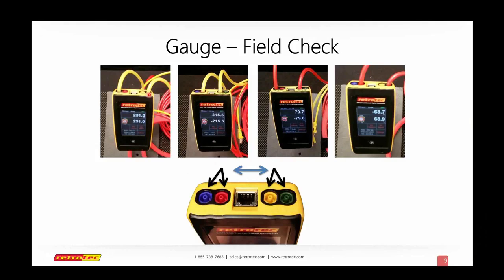And this is commonly known as the port-to-port test. So what you'll see on your gauge, if it's set for pressure on channel A and pressure on channel B, is that they should both be about the same readings, within about 2%. And here you have a different configuration where we're plugging into a different port, connected to a different port, and so on. And you'll notice that here we are testing our yellow cords, and here we're testing some blue or some red cords. And the point being that we're not only testing to make sure that our gauge is calibrated, or in calibration if you're a rater, but we're also making sure that our tubes don't have any holes or cuts or any kind of problems.